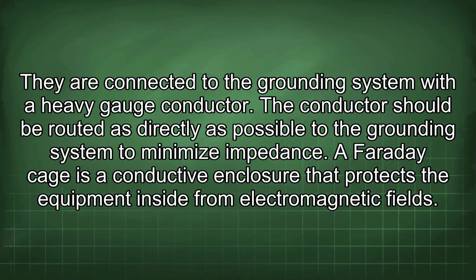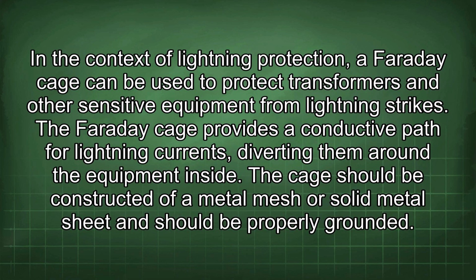A Faraday cage is a conductive enclosure that protects the equipment inside from electromagnetic fields. In the context of lightning protection, a Faraday cage can be used to protect transformers and other sensitive equipment from lightning strikes. The Faraday cage provides a conductive path for lightning currents, diverting them around the equipment inside. The cage should be constructed of a metal mesh or solid metal sheet and should be properly grounded.